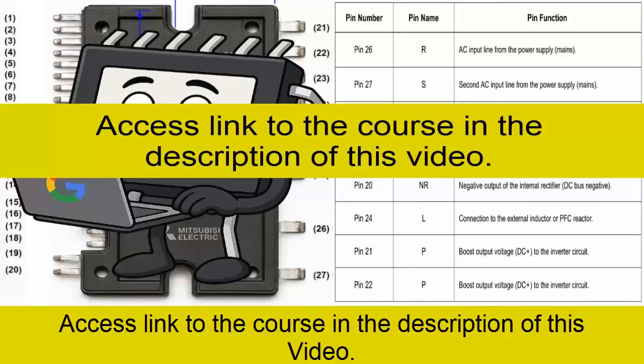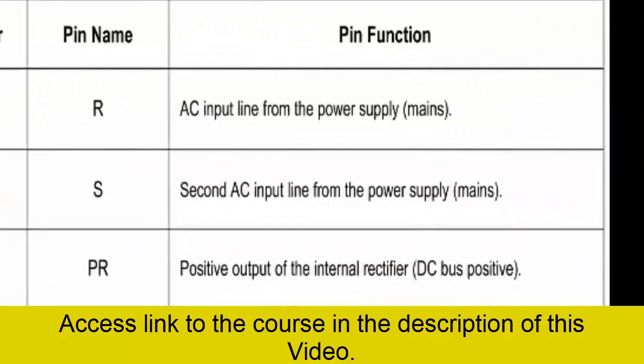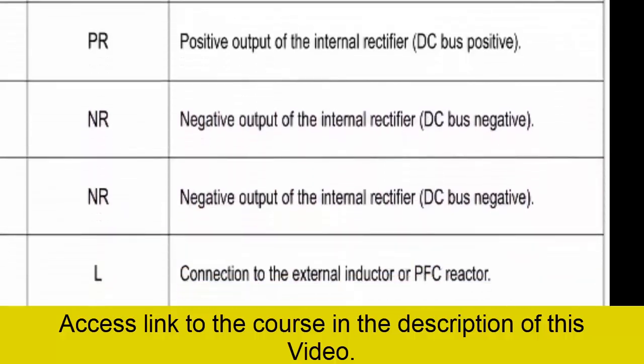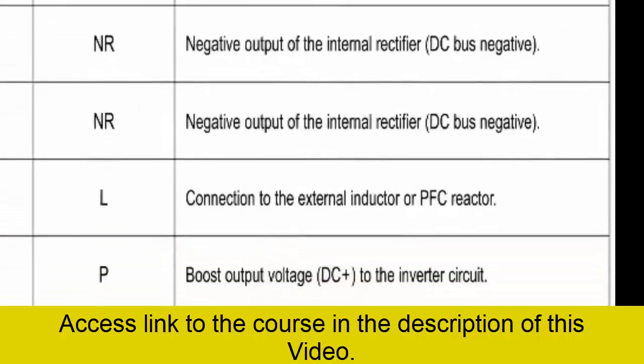To correctly perform the PFC circuit tests, it is necessary to first identify the main terminals of the module: R and S pins, the AC alternating current inputs coming from the electrical power line; PR pin, the positive output of the internal rectifier; NR pin, the negative line of the internal rectifier; L pin, the connection to the external PFC coil or reactor; and P pin, the final positive voltage output to the inverter circuit.